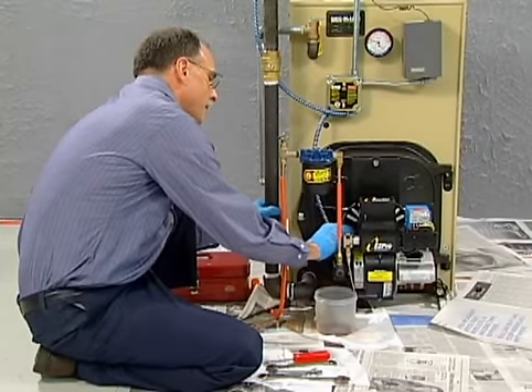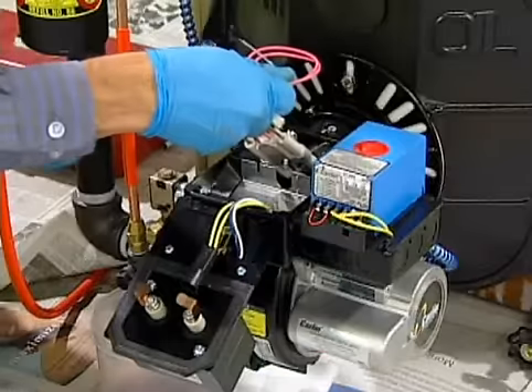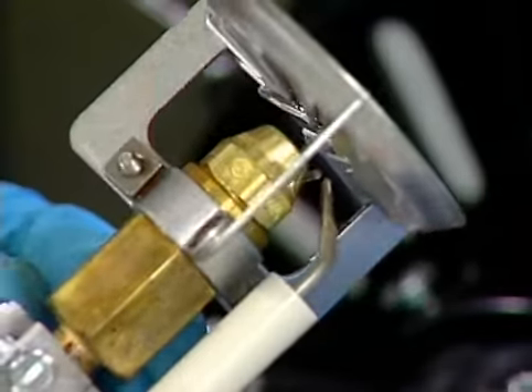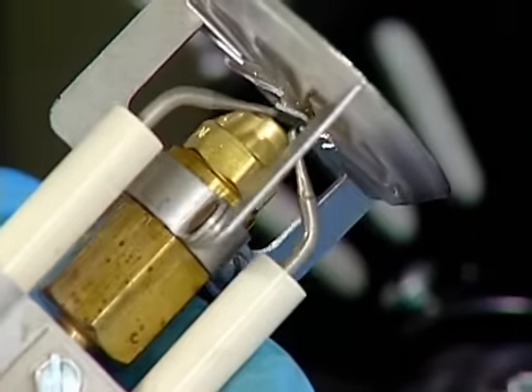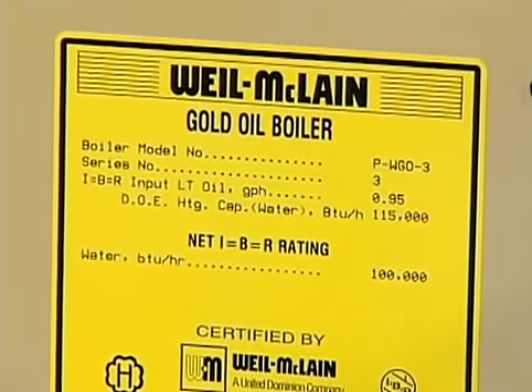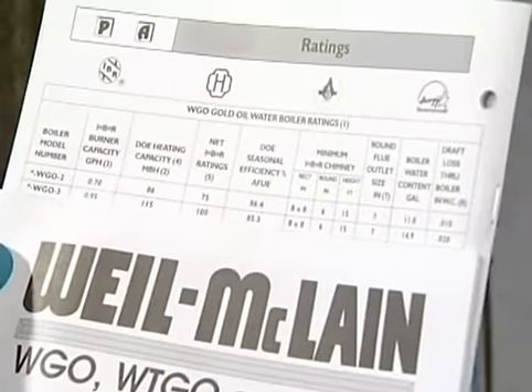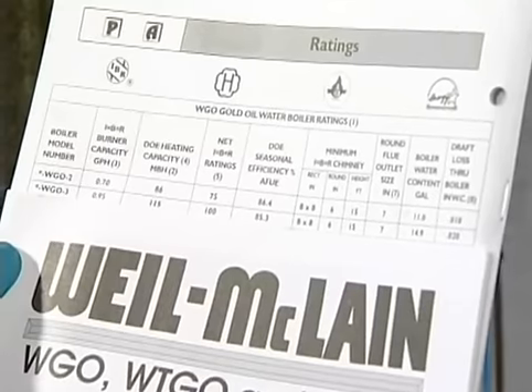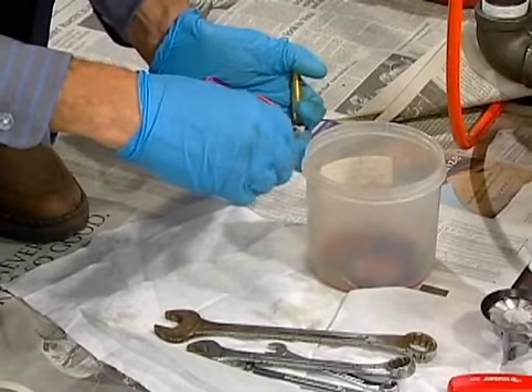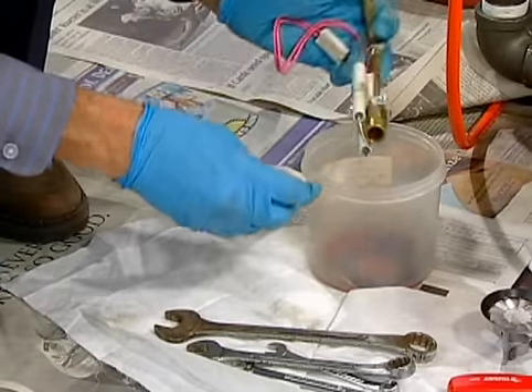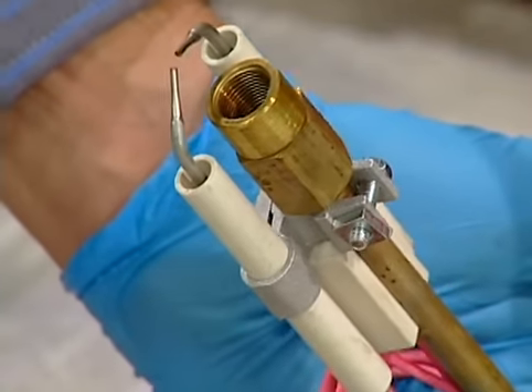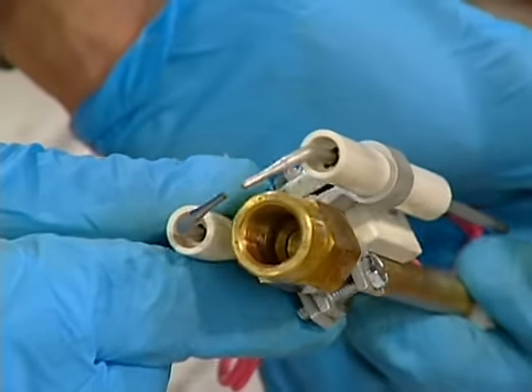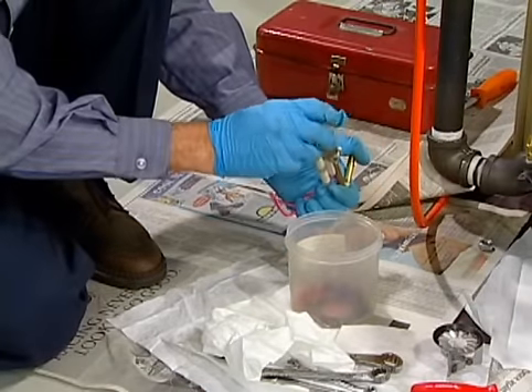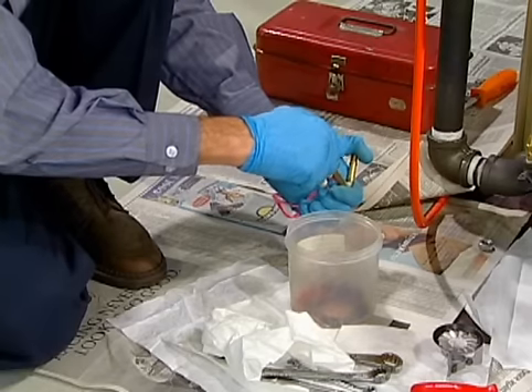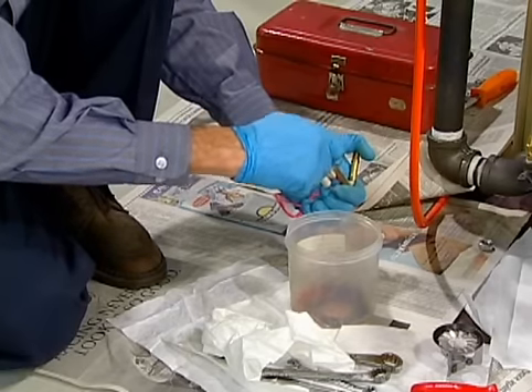Mark the position of the firing assembly on the burner housing, remove the nozzle assembly, and note the nozzle type, size, and spray angle, verifying that these match the unit data plate or the listing in your manufacturer's OEM guide. Remove the nozzle and carefully drain the oil into a container. Inspect the nozzle adapter, replace it if it's stripped, cracked, or if the seat is worn. Install a new nozzle, handling it carefully so you don't damage the orifice or contaminate the strainer.